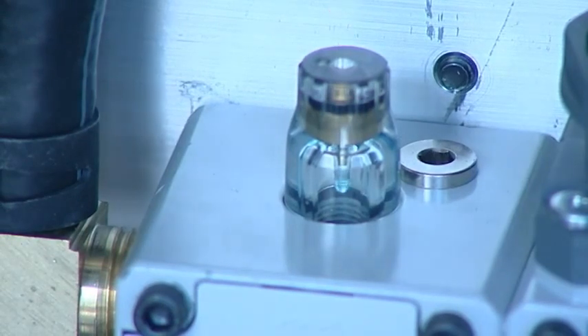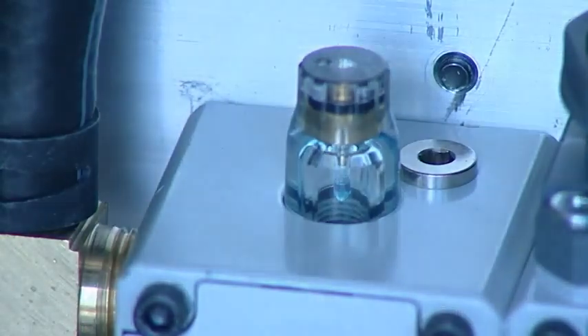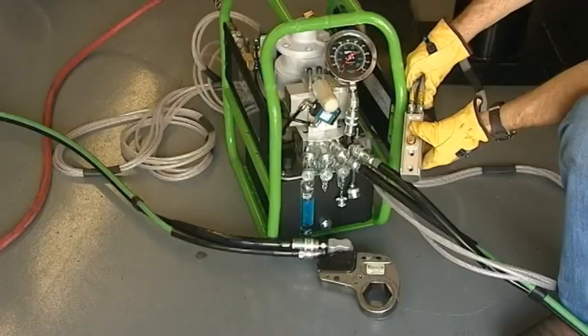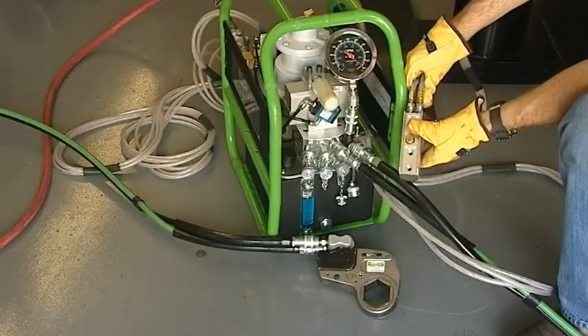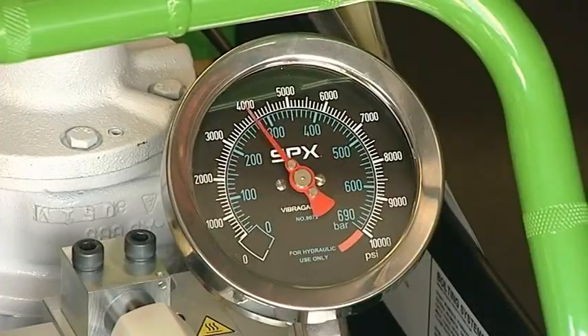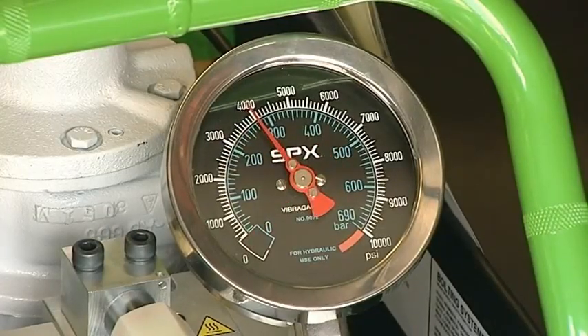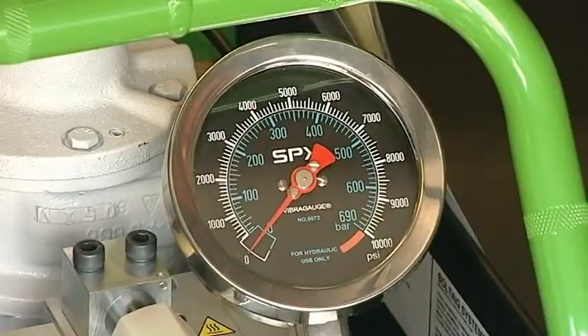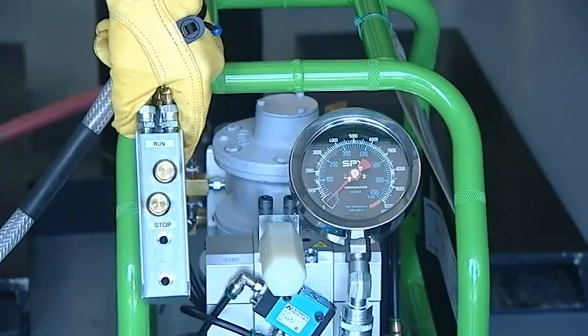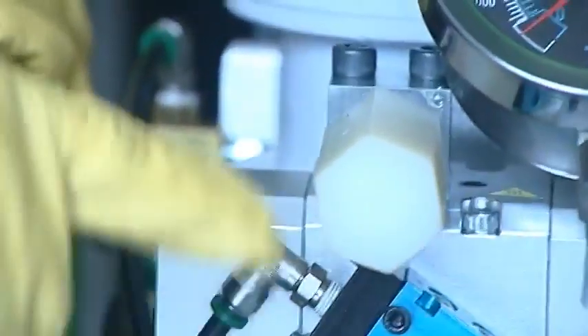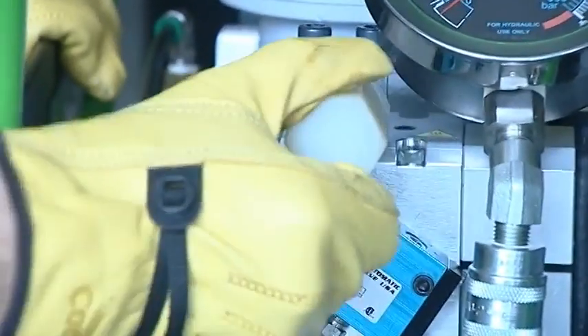Once the lubricator drip is set, stand back and hold down the advance button to build pressure to 10,000 psi. If the pump does not build pressure to 10,000 psi, release the advance button and push the off button once to turn the pump off. With the pump off, turn the torque control valve clockwise to build more pressure. Repeat the pump operation.